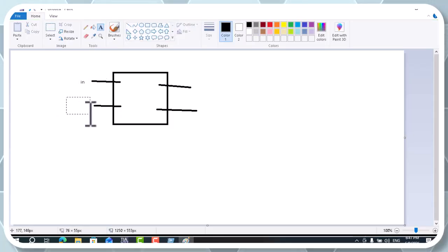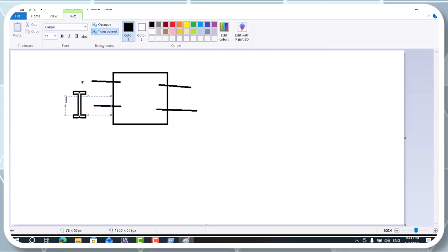Next one is the PT signal. PT is the preset time that we will set for our timer, and it uses 32 bits, and also we use it like the int. It means that you can adjust time up to 24 days and 20 hours, as I remember.